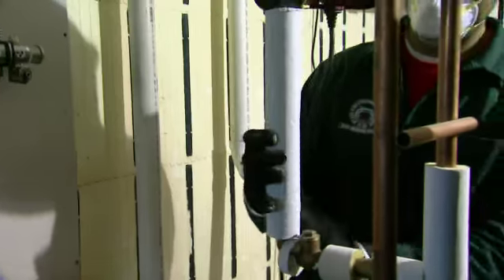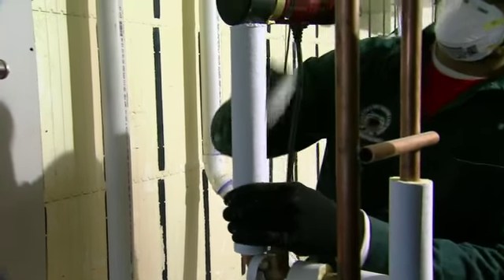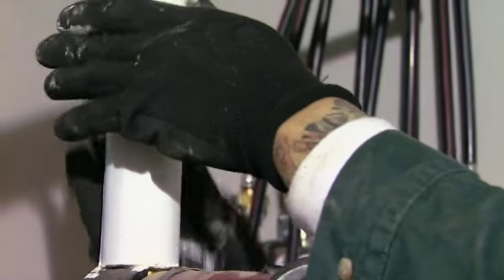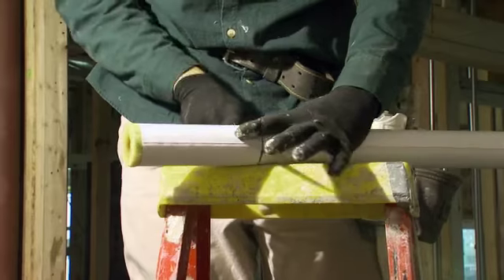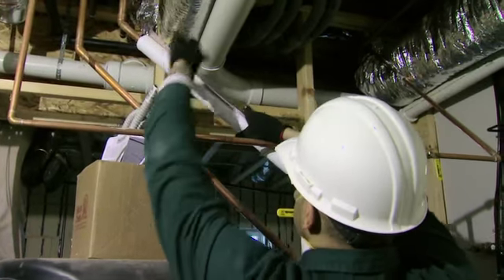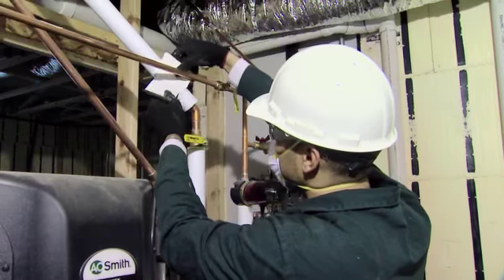The typical pipe covering, as we call it, or pipe insulation, is fiberglass, and it's got a paper backing applied to it, which is an all-service jacket, which helps for, obviously, aesthetics, but it also protects the fiberglass underneath it. And it has a vapor barrier built into it, so it'll stop condensation and mold growth from the insulation itself absorbing or holding any moisture.